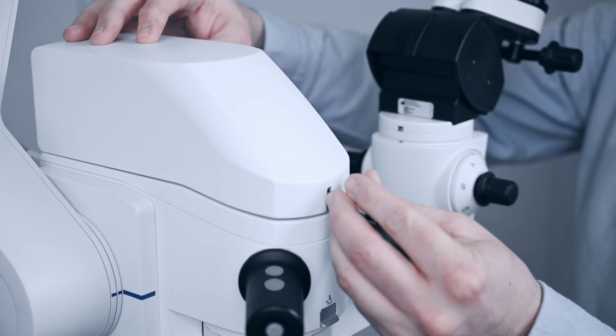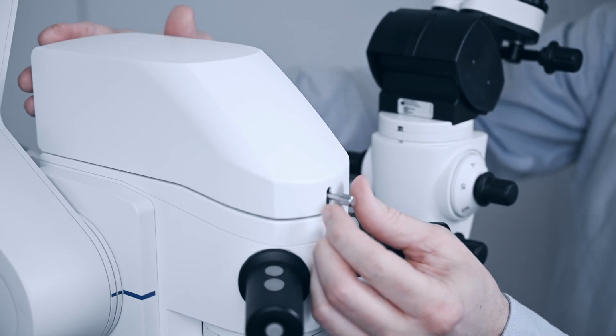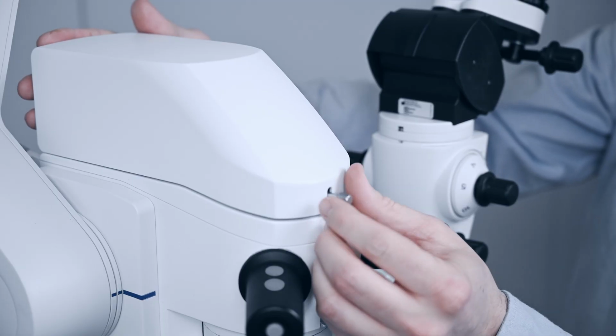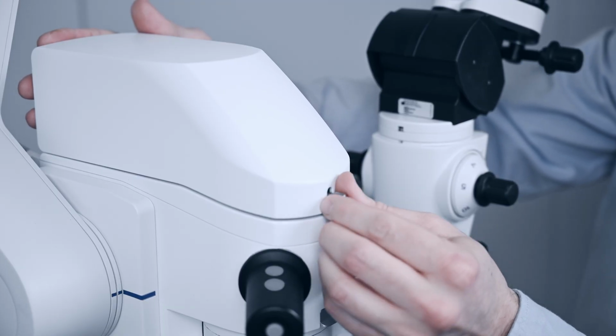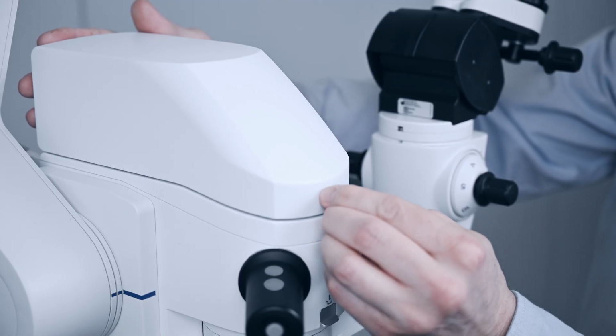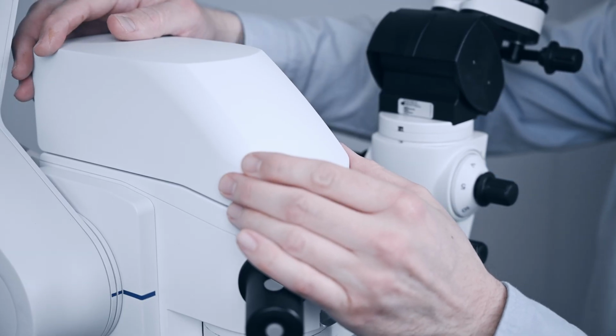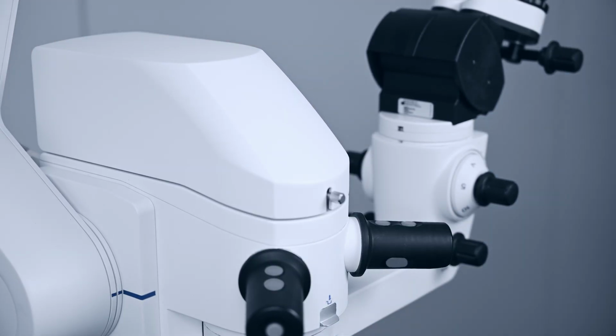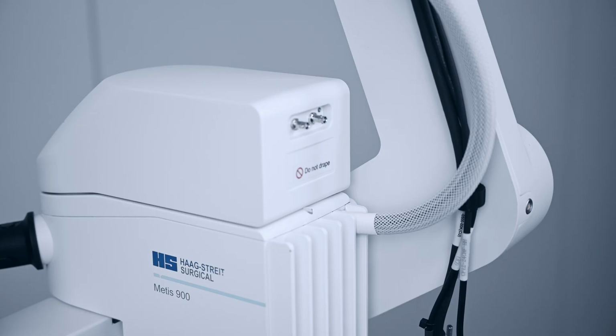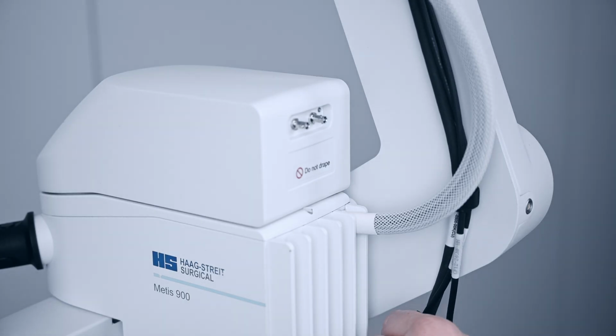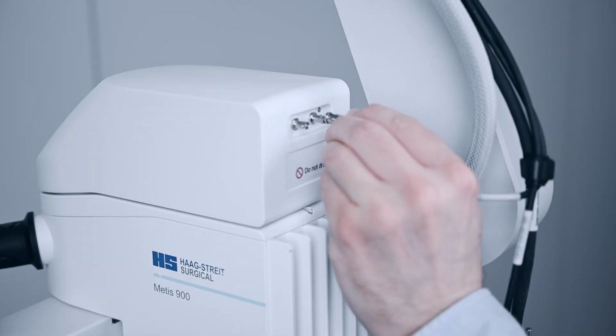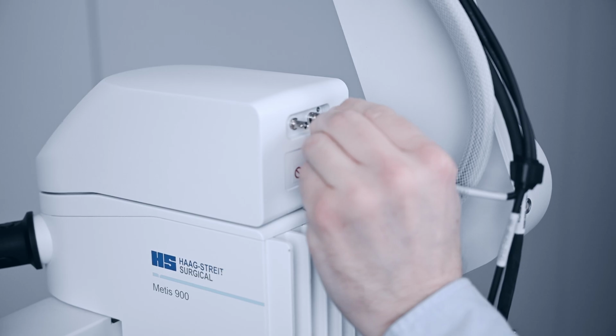Now, gently tighten the knurled screw by hand in a clockwise direction. You must make sure that the stereo camera unit sits tightly on the microscope now. You should not be able to move it or lift it off. Next, align the bayonet slot of a CXP plug with a CXP connector of the stereo camera unit. Now push the CXP plug onto the CXP connector and turn it clockwise to lock.